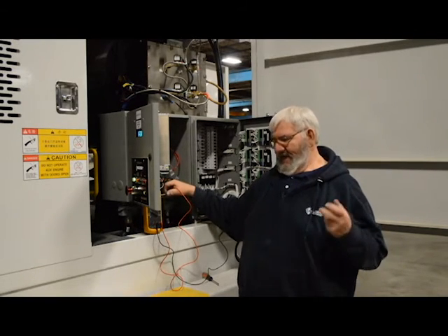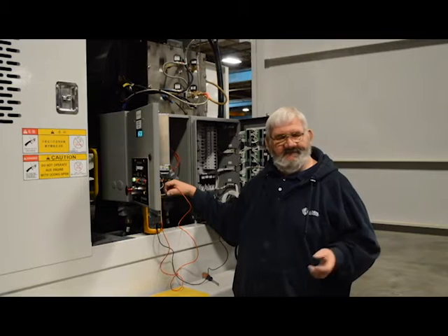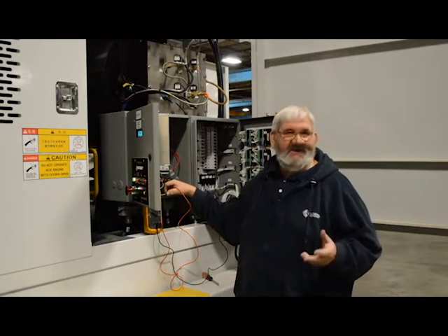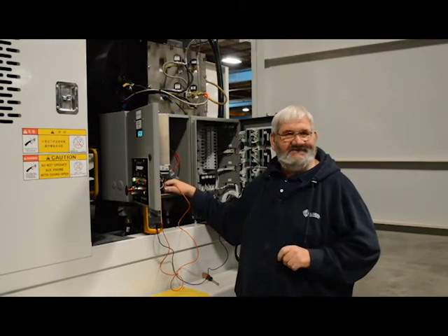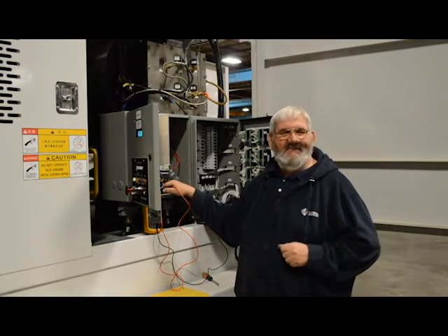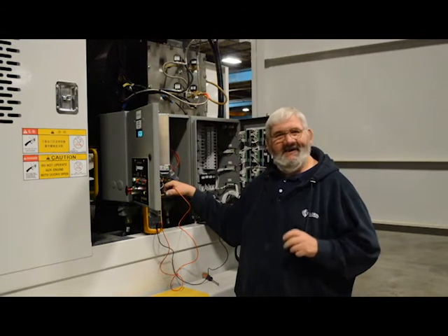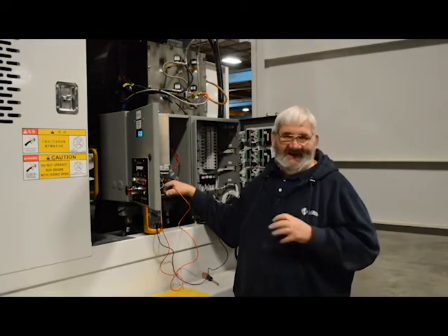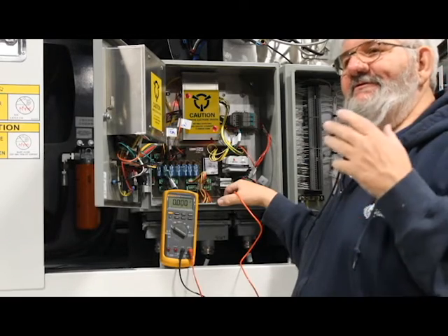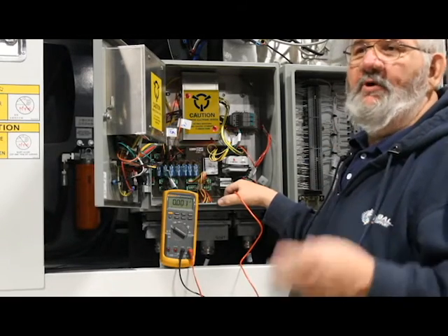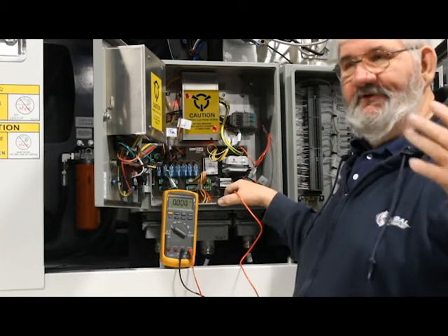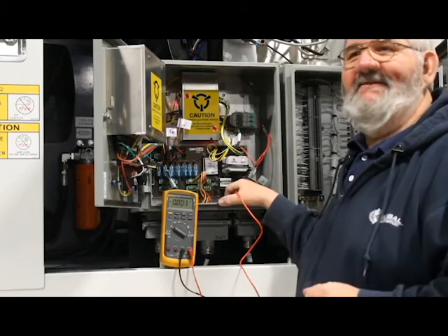Typically, what happens with the RTDs, inside is what we call a transmitter. It's nicknamed the hockey puck. It's about 3/8 inches thick, about 1.25 inches in diameter. Normally that hockey puck or transmitter is what goes bad. It's not the whole RTD. Also keep in mind that you could also have a broken wire, or you could have wires that are shorted together. So do your troubleshooting. This will help identify the problem.